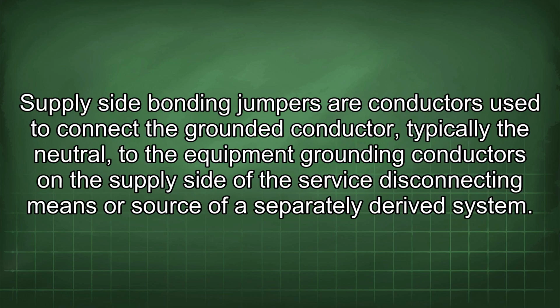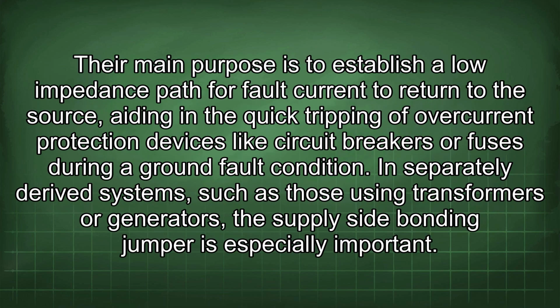Fourthly, supply-side bonding jumpers. Supply-side bonding jumpers are conductors used to connect the grounded conductor, typically the neutral, to the equipment grounding conductors on the supply side of the service disconnecting means or source of a separately derived system. Their main purpose is to establish a lower impedance path for fault current to return to the source, aiding in the quick tripping of overcurrent protection devices like circuit breakers or fuses during a ground fault condition.